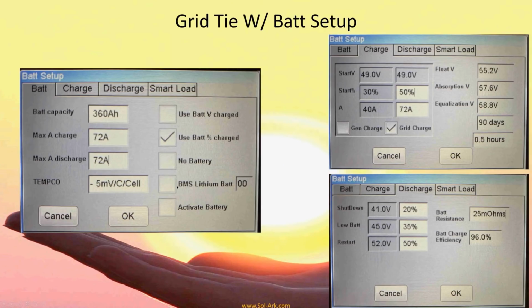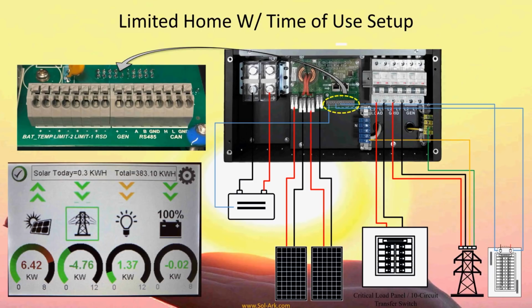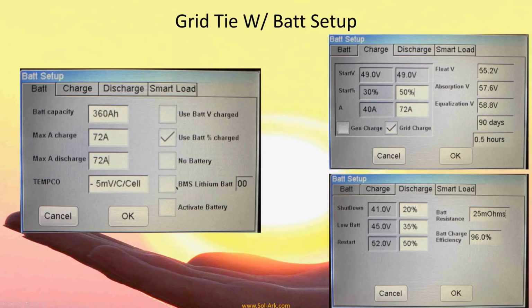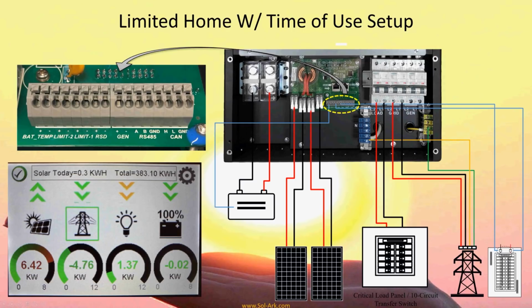If I'm going to communicate to a lithium battery that has a communication bus, I will turn this on, and sometimes I need to activate the battery to turn it on as well. That way I'm able to read back the SOC and the temperature from the battery. That's mainly all it's used for. If I'm not able to communicate to the battery, let's say I accidentally turned this BMS lithium battery setting on, you will see an exclamation point here, meaning something's weird with the battery.